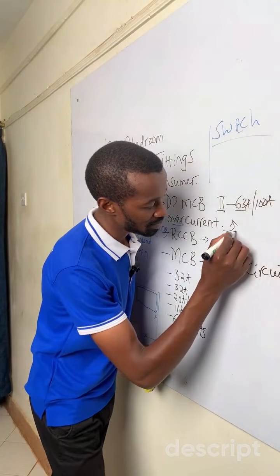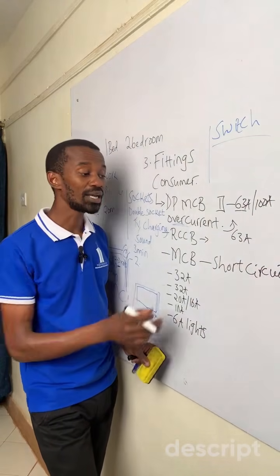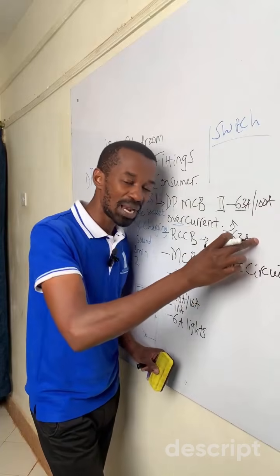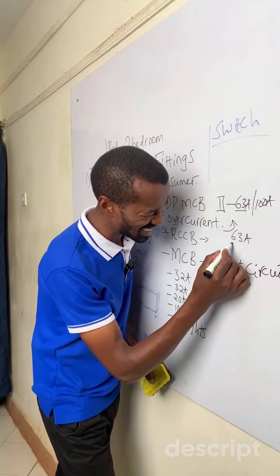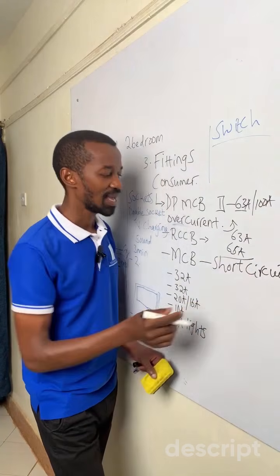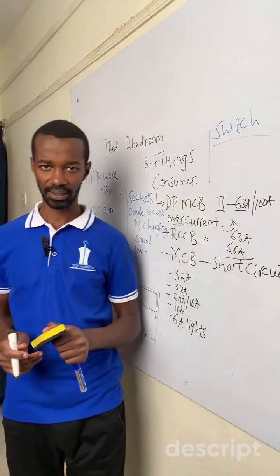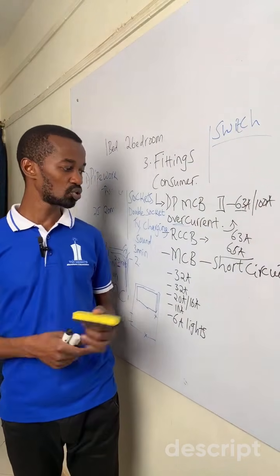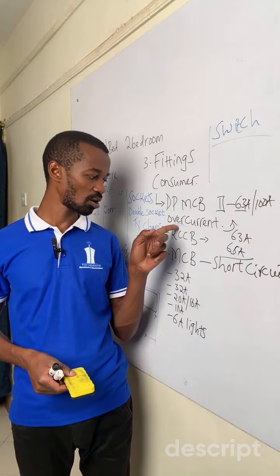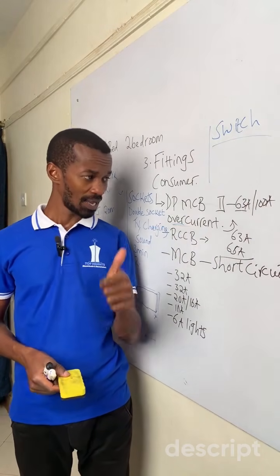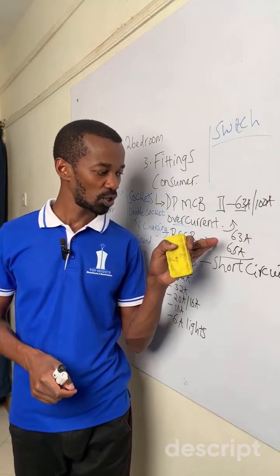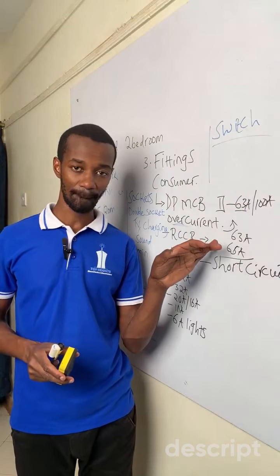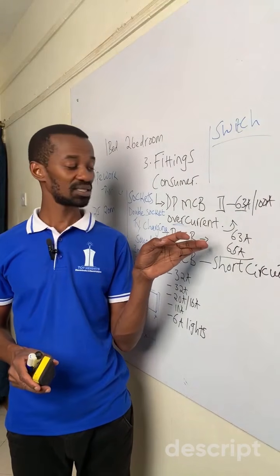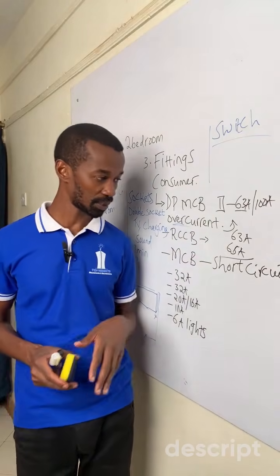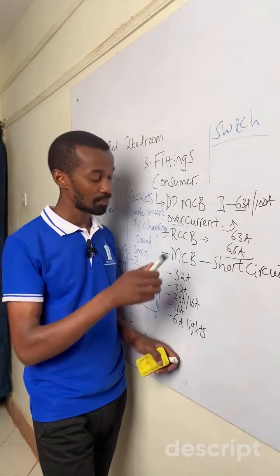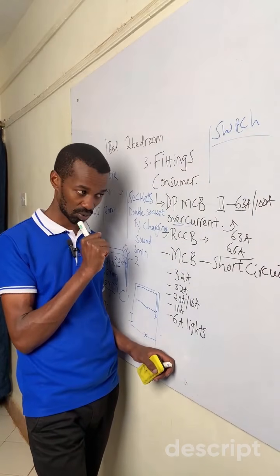So assuming the DP MCB is rated at 63 amperes, and you connect a washing machine, a cooker, instant showers, plus a water pump, and that current exceeds or goes all the way to 65 amperes, the DP MCB will detect an overcurrent. It will automatically trip to protect against issues like overheating. If it trips, the electrician has to come and troubleshoot — did you invite him? In many cases it's not good for you to keep lifting these devices up yourself, so engage an electrician to find what made the DP MCB trip. Was there a short circuit that was heavy?